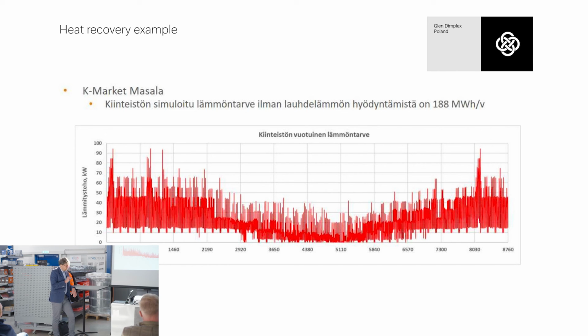And what is also interesting is that during the summer we also need a lot of energy for warming up the ventilation air, for example, just after dehumidifying the air using the cooling heat exchanger, we need to warm up the inlet air for ventilation a little bit. So also during the summertime we have quite a big heating energy demand.